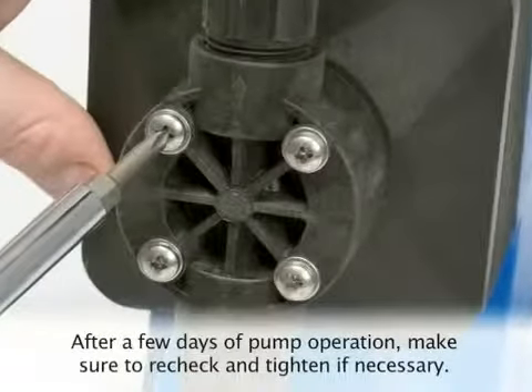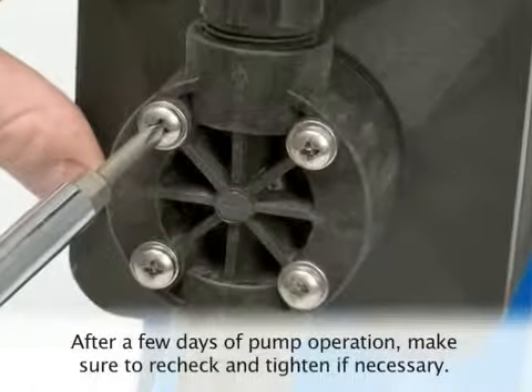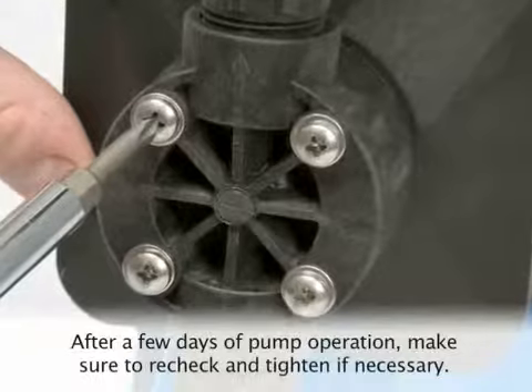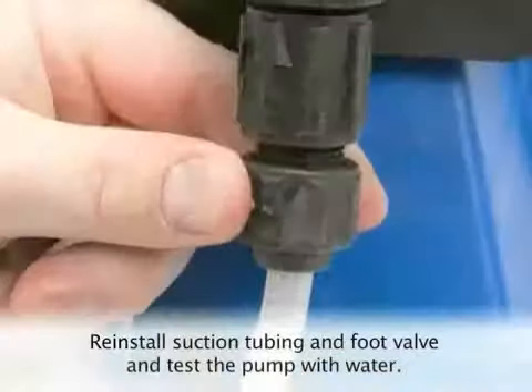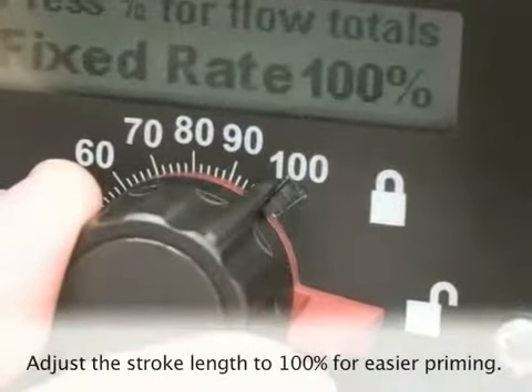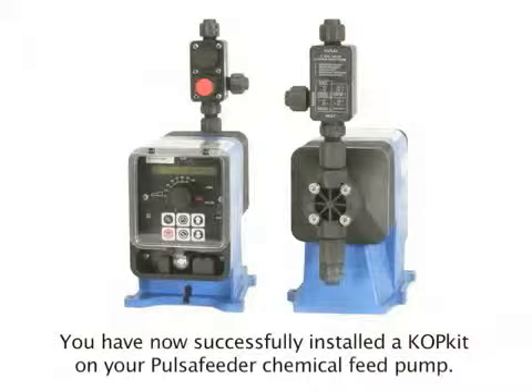After a few days of pump operation, make sure to go back and recheck the head screws and retighten them if necessary. Reinstall the suction tubing and foot valve and test the pump with water. Adjust your stroke length to 100% for easier priming. You have now successfully installed a COP kit on your Pulsafeeder chemical feed pump.